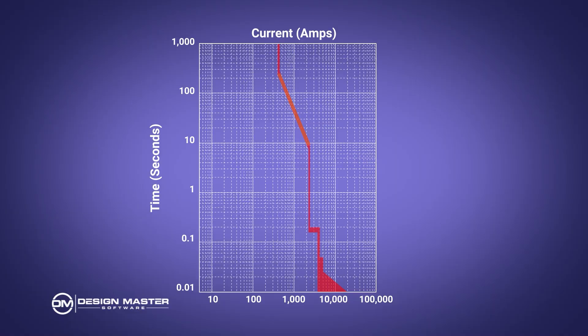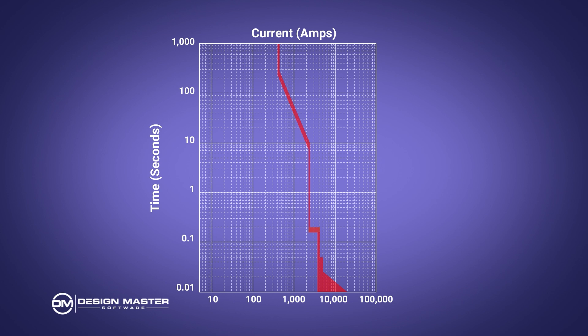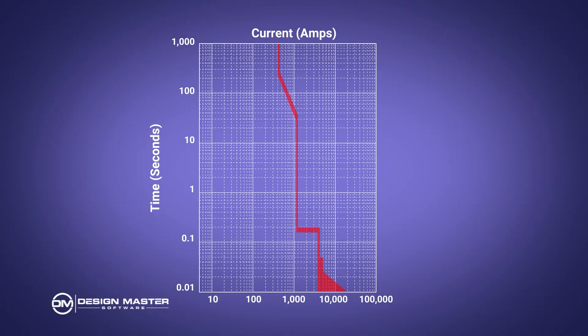Then you have the long time delay — the first sloped section — and depending on the breaker you have options to move this sloped value up and down on the curve. Then you have the short time pickup, the next vertical line, which you can move left and right. After that is the short time delay, a horizontal line after the short time pickup that you can usually move up and down. Depending on the type of breaker, you can also have an I² T curve, which is a sloped line between the short time pickup and short time delay.